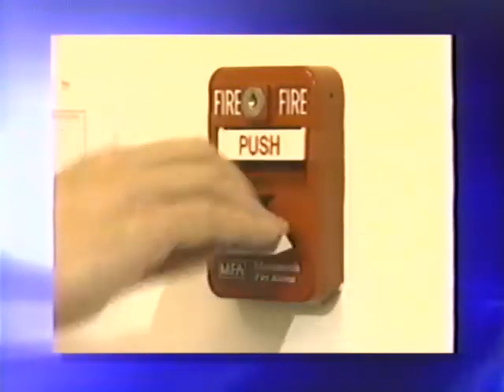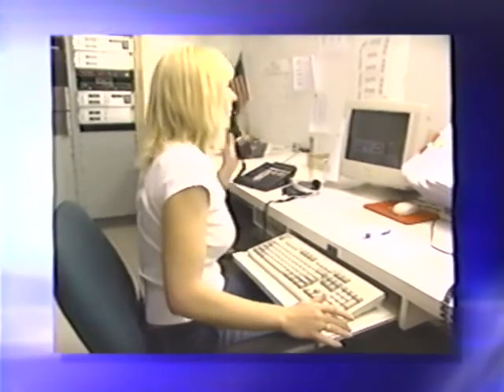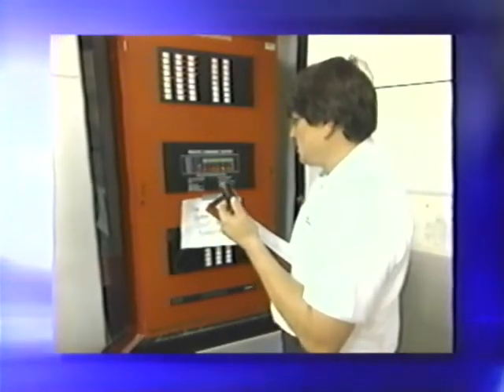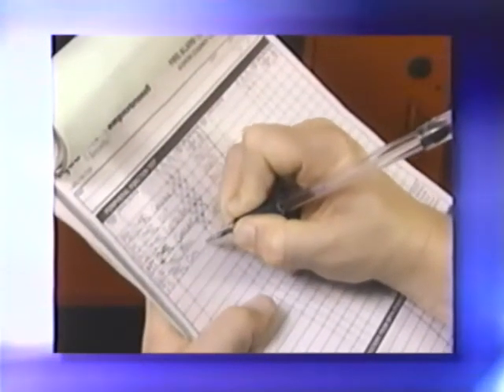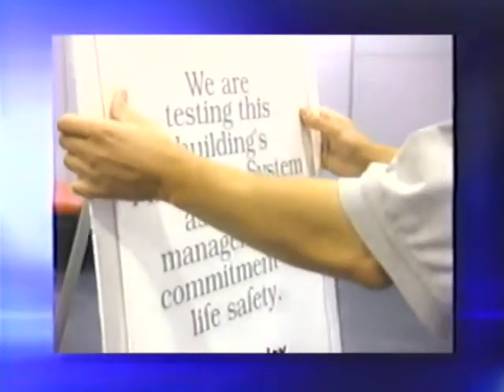As technology has advanced, fire alarm systems have become more sophisticated and complex. It's essential to have a program in place for the regular inspection and testing of all system components: initiating devices, control units, notification appliances, and equipment for off-premises transmission of a signal. Develop an inspection and testing checklist tailored to the facility and notify anybody who will be affected that testing is taking place.